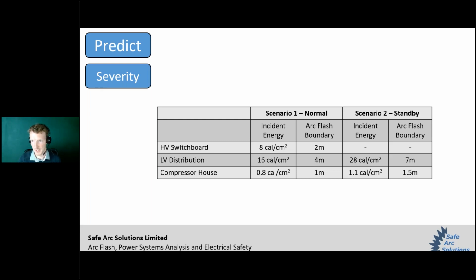And it's important to take into account, as I say, these different scenarios. You can see that for the LV distribution, the incident energy is quite different between the two scenarios. The fault current characteristics of the standby generator are quite different to in the normal scenario. So it's important to capture that kind of detail.